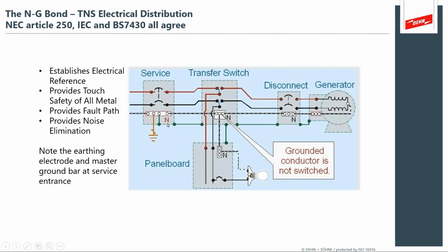In doing site inspections, you can sometimes see where the electrician might have made a mistake and had a duplicate earth neutral ground connection, or perhaps mixed the ground and the white and the green wire, for instance, in the electrical system. So an illustration like this is really important to point out bonding. The neutral ground bond is for electrical safety, and it's a single point of neutral ground bond, and that's common throughout the standards.